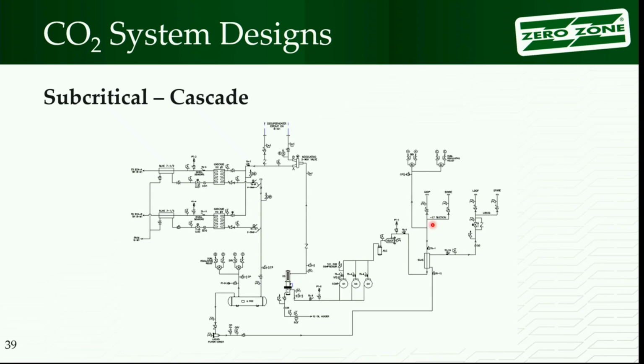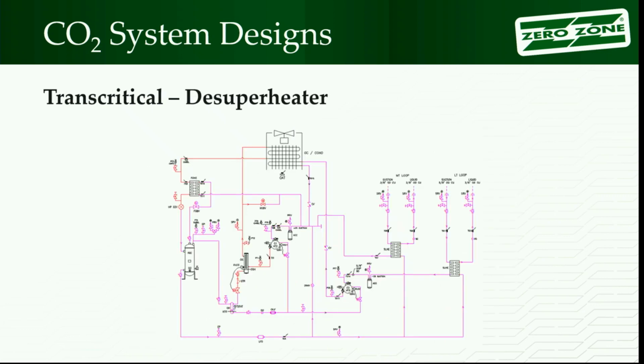When you go into troubleshooting, okay, that one's got a heat exchanger on, there's something wrong with the heat exchanger, is it cracked, is it bleeding? The diagrams help you see all that without trying to follow this maze of black snakes. Very difficult. This guy here, again, where you look for safety valves, we have safety valve protection. The safety valve in that suction line actually shows up on the accumulator. So again, pretty easy to spot on the diagram.